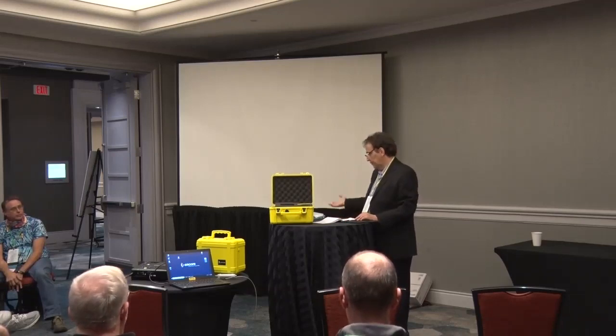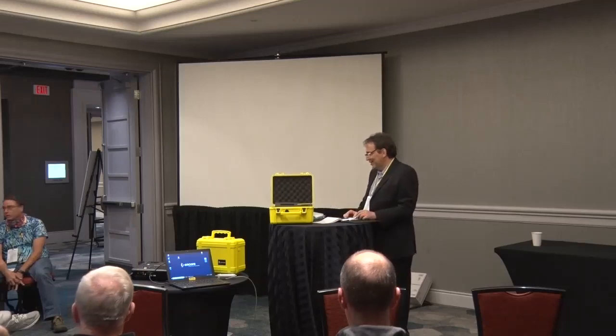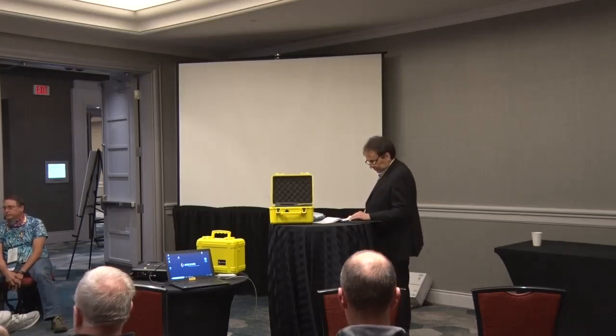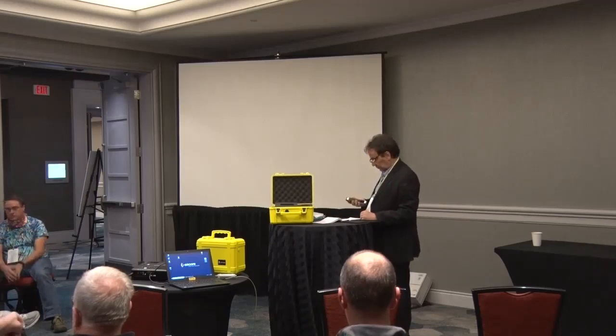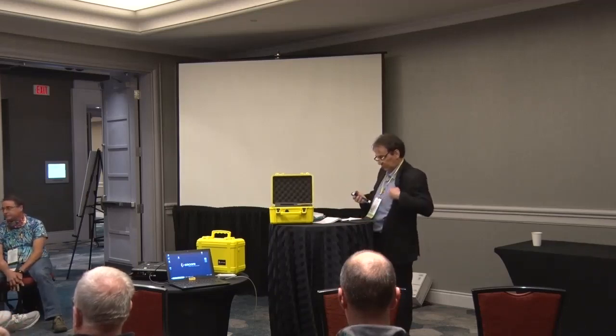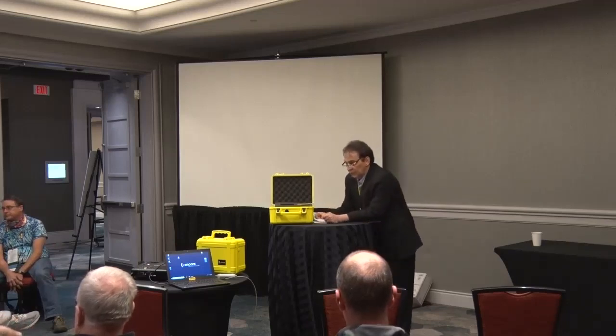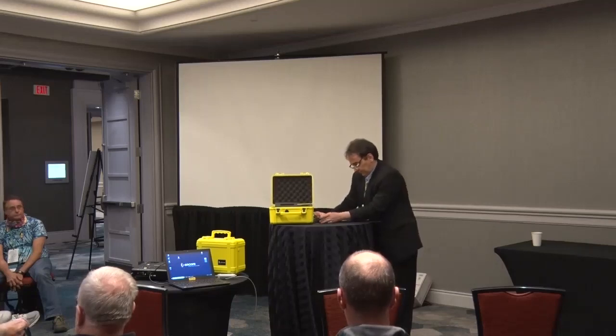It's nice if you have a finished basement, you don't have to deal with it. You could make your own kind of blower door, just something that goes over the window, over the basement door that just sucks enough air out of it. Sometimes the air handlers are already getting 4 or 5 Pascals. And they've got the floor pan return ducts. I always check on that, I'm like, oh, you got a problem house, let's check whether the basement's being depressurized by the furnace, and check the mitigators.